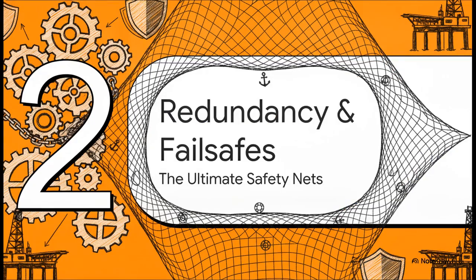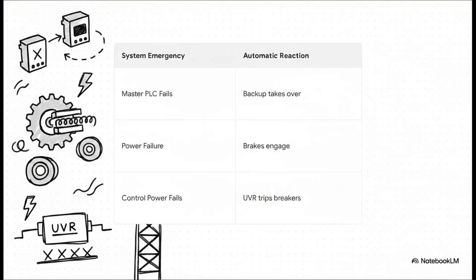That brings us right into Section 2, Redundancy and Fail-Safe Layers. Let's look at the ultimate safety nets. This system is packed with some incredible survival instincts built directly into its hardware and logic. Check this out. If your master PLC drops offline due to a hardware fault, there's a second identical 1756L73 backup sitting right there in hot standby.